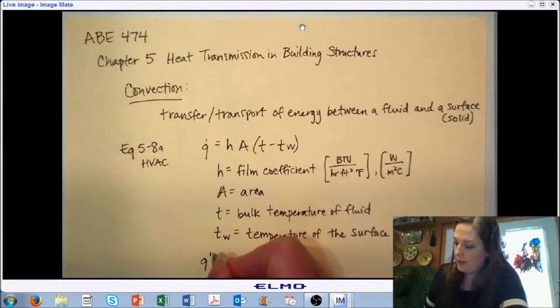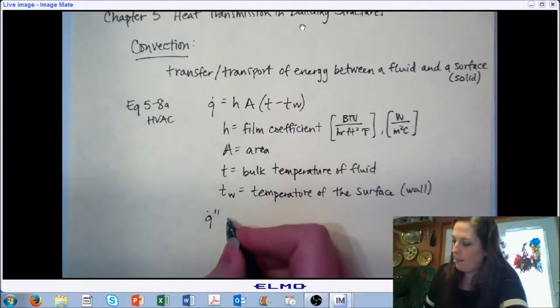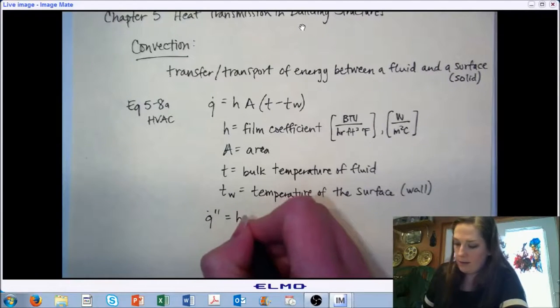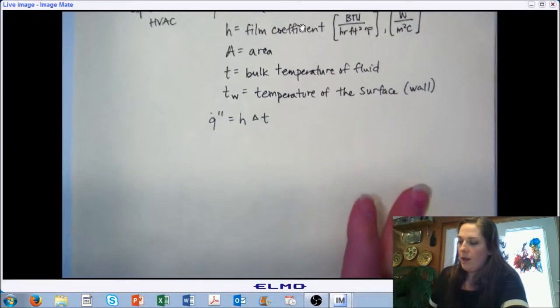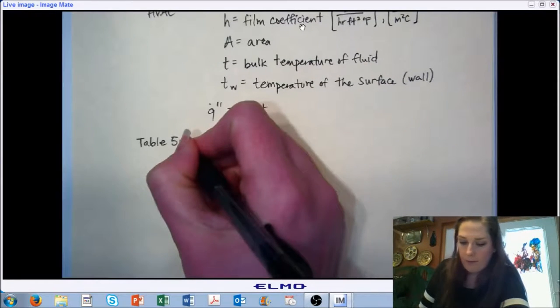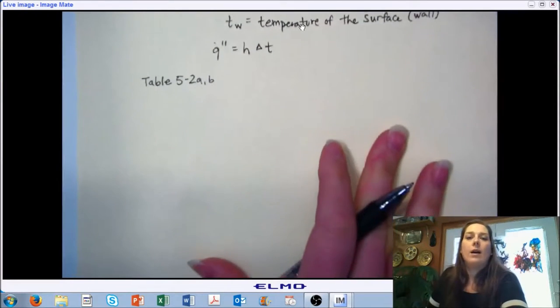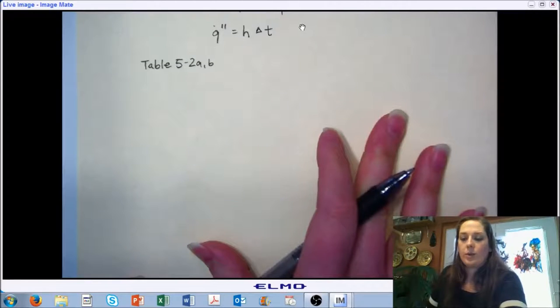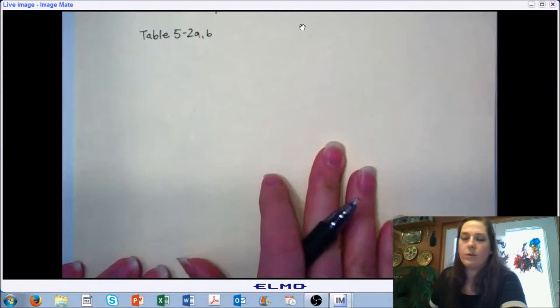This equation is on a total heat transfer basis. If we want to look at it on a per unit area basis, we essentially use h·ΔT. In our book, to get some representation of these film coefficients, Table 5-2A and B provides typical values we're going to be looking at whenever we're analyzing convective heat transfer on the surface of one of our walls.